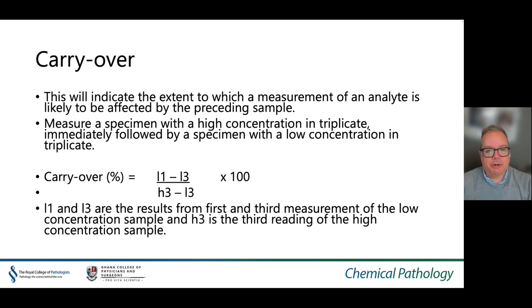Carryover indicates the extent to which a measurement of an analyte is likely to be affected by the preceding sample. This can be particularly important in measurement of high-concentration compounds such as tumour markers or in toxicology. Ideally, you would measure a high-concentration sample in triplicate immediately followed by a lower-concentration specimen also in triplicate, and carryover percentage can be determined by the indicated formula. In this formula, L1 and L3 are the first and third measurements of the lower-concentration sample, and H3 is the third reading of the high-concentration sample.